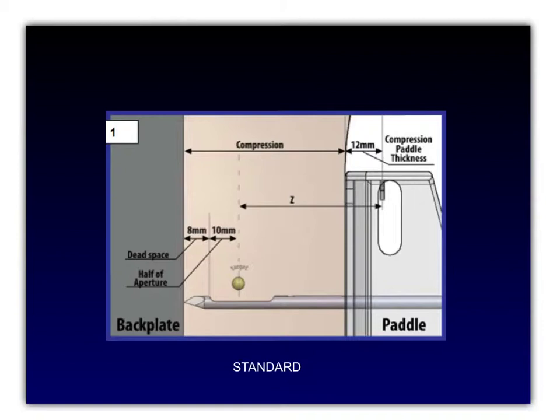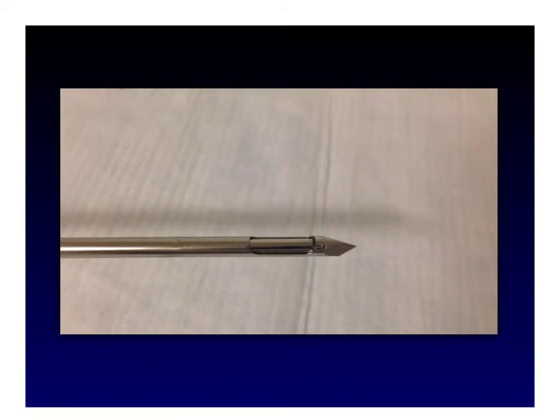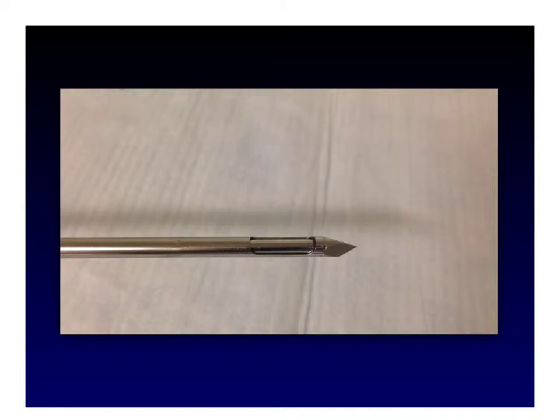The biopsy device is fired in the breast. The distance the device travels is called the stroke. Once in the post-fire position, tissue gets sucked down into the well and a cutting portion cuts over the tissue. To perform the biopsy, you fire it, then press and hold your foot on the pedal — that activates the vacuum, then the cutter, and a beep indicates you can adjust the biopsy device. To stop sampling, you take your foot off the pedal.